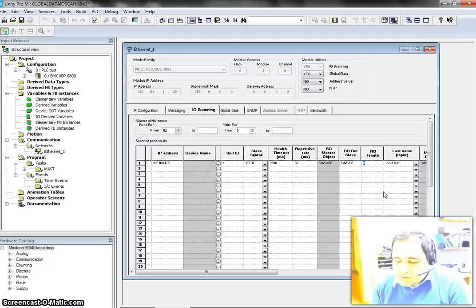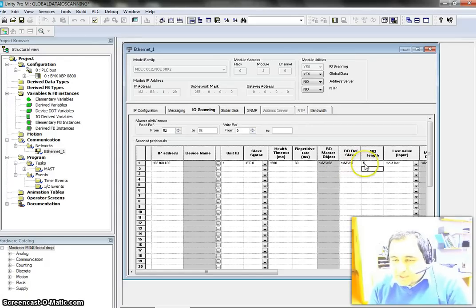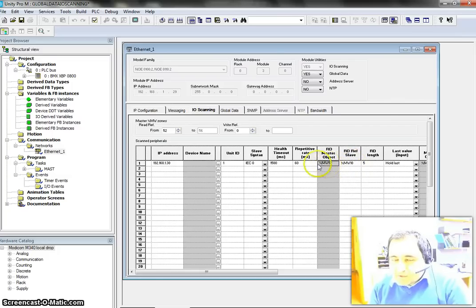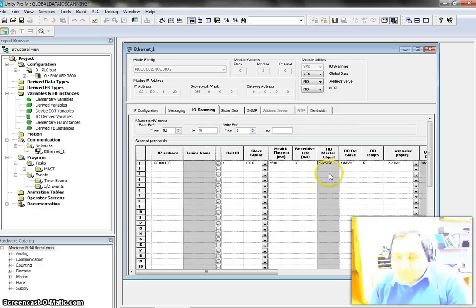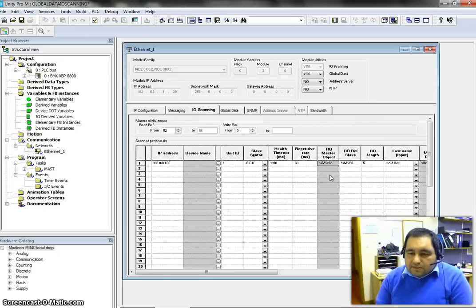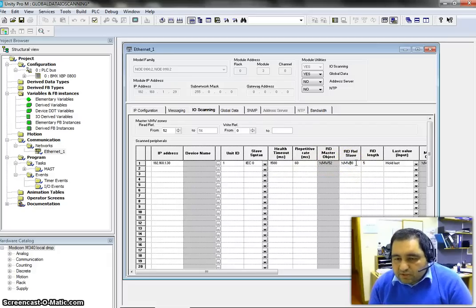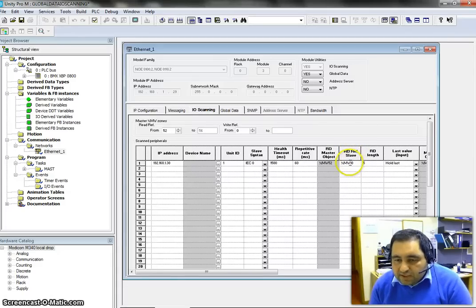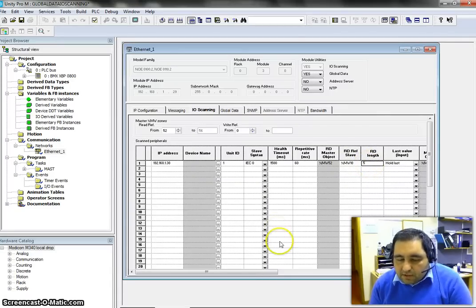Then we set the read length — how many words we want to read. For example, if we set the length so that the last address is 57, then master memory addresses 52 through 57 are going to hold all the information located in the slave device from memory word 10 until memory word 15, because of the length that we have set.